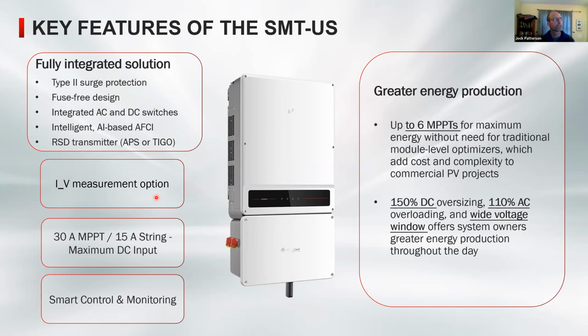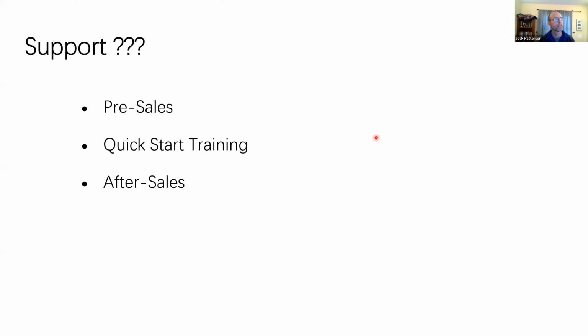I talked about our residential inverters being able to handle these 12.5 amps. For this, we're talking 15 amps per string. Now, if you happen to get a module, and they're out there and they will be out there, that's more than 15 amps, it just means you're doing one string into an MPPT rather than two. So the MPPT is 30 amps overall, which means we can handle very powerful modules. Most of them are still going to be under 15 amps, so you're going to be able to put two strings per MPPT. And you have 5 or 6 MPPTs, whether you're doing the 50 or 60. So the two sizes are 50 and 60 kilowatts. So that represents the C&I, and I'm happy to take questions.